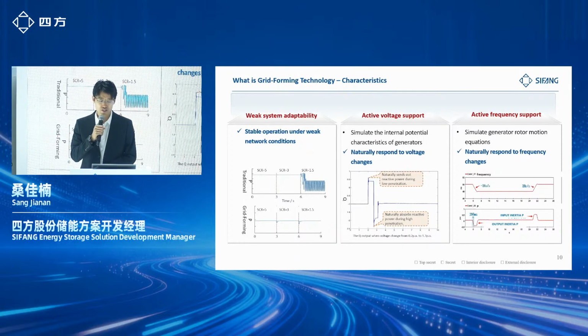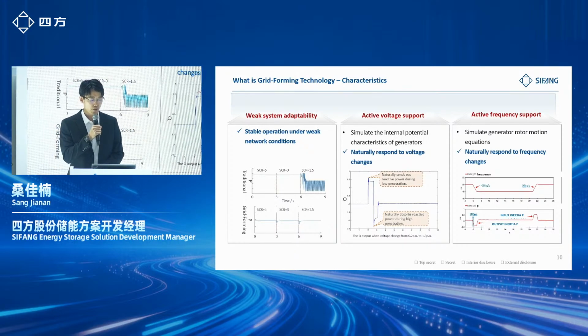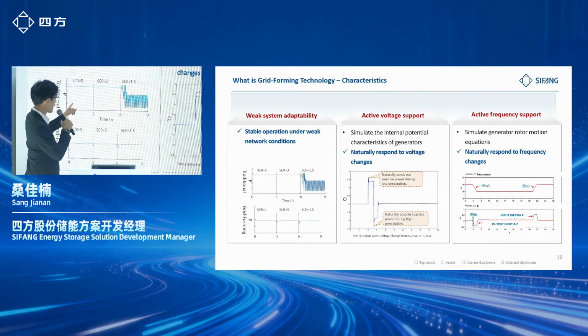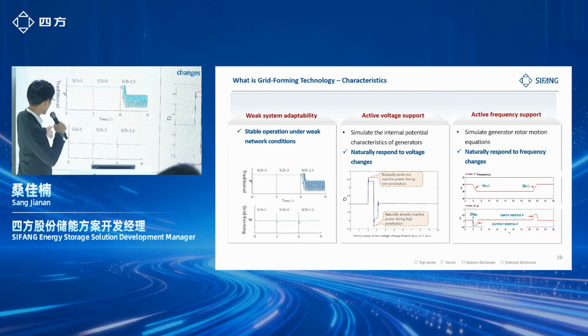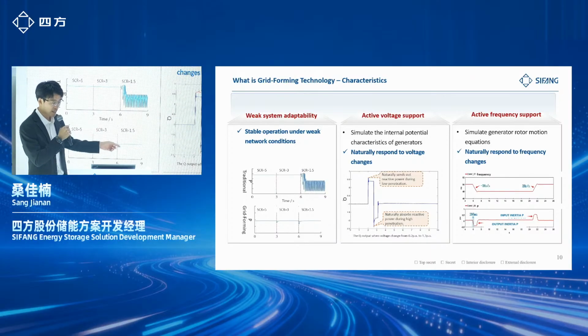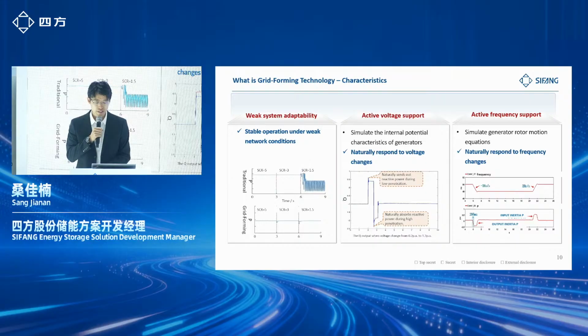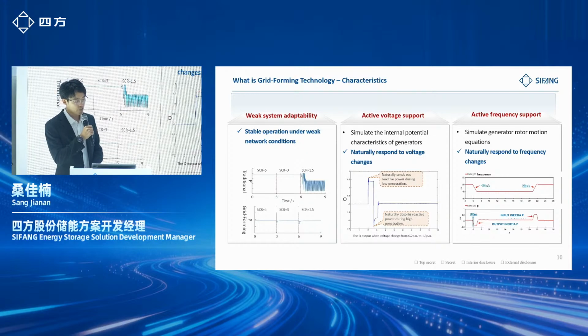So what are the characteristics of grid-forming technology? The first is weak system adaptability. You can see the traditional one, the upper one: when the SCR is lower, it leads to fluctuation. But the grid-forming one can always operate even when the SCR is very low. Second and third are voltage and frequency support. Because it is just like a voltage source, it can naturally respond to voltage and frequency changes.